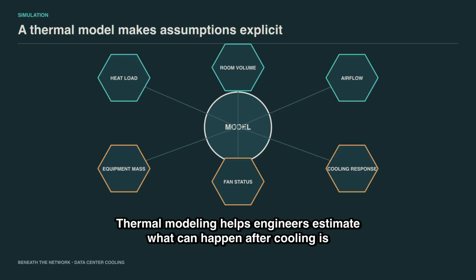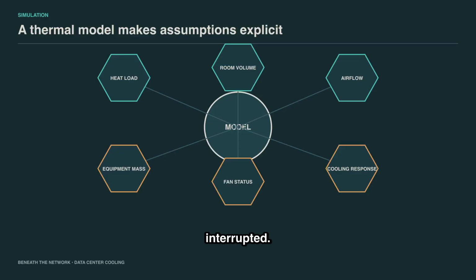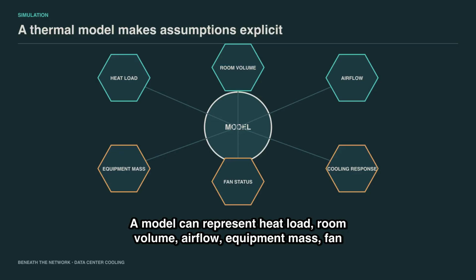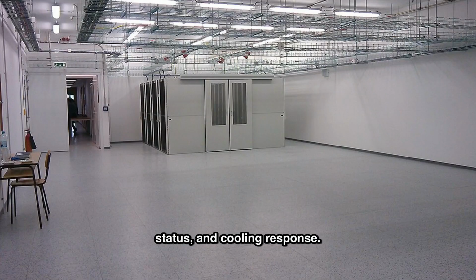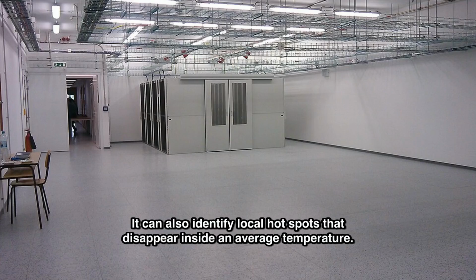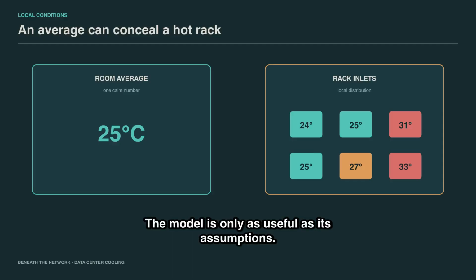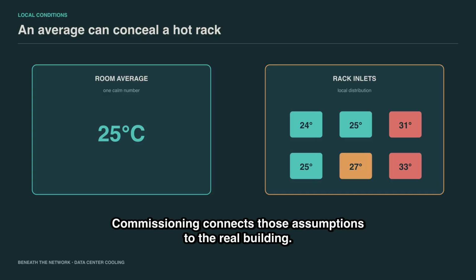Thermal modeling helps engineers estimate what can happen after cooling is interrupted. A model can represent heat load, room volume, airflow, equipment mass, fan status, and cooling response. It can also identify local hot spots that disappear inside an average temperature. The model is only as useful as its assumptions. Commissioning connects those assumptions to the real building.